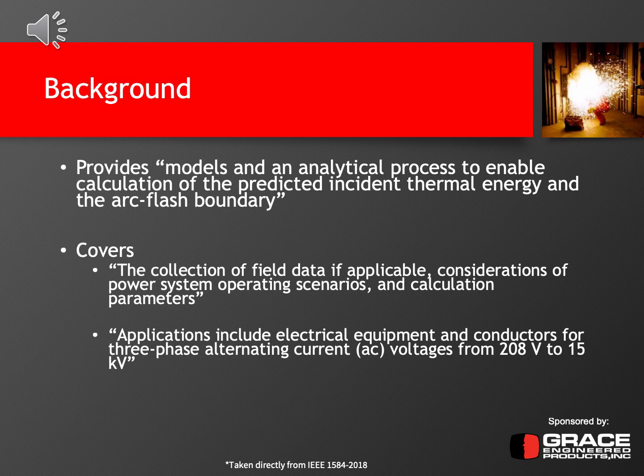One thing that also needs to be discussed is the number of operating scenarios and which operating scenarios are likely to be investigated. The ideal situation is you'd like to get all the operating scenarios, but there's going to need to be some input from the client on which operating scenarios they operate in. It might be just a couple, like a normal and an emergency, or it might be one source on, one source off, or both sources on, depending on how it's all configured. And then it also covers the parameters necessary to perform these calculations, and we'll get into that in a little bit. The application of this includes electrical equipment and conductors for three-phase alternating current, or AC, voltages from 208 volts up to 15,000 volts, or 15 kV. That's the bounds of this standard.